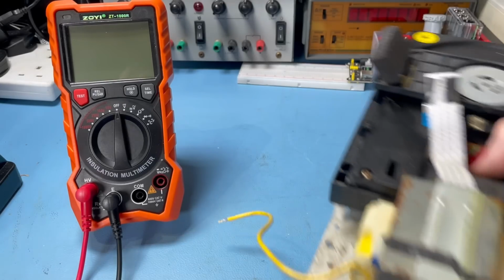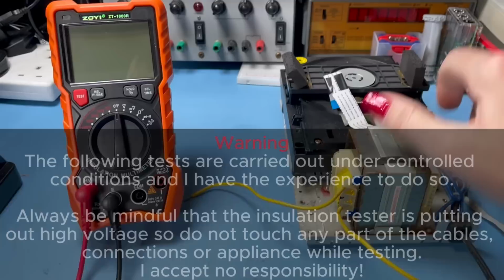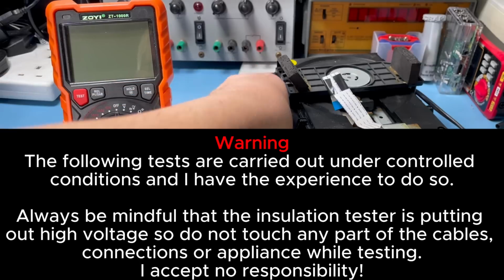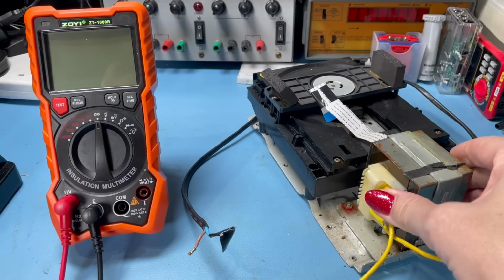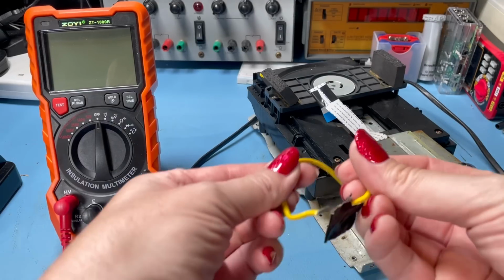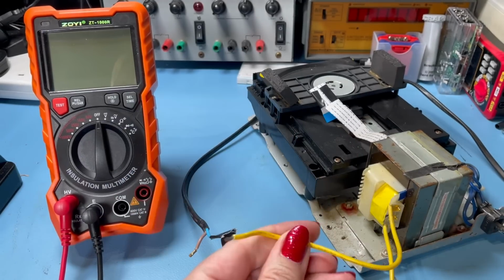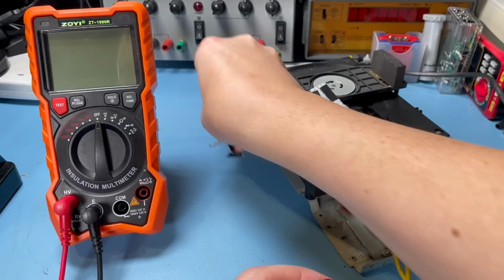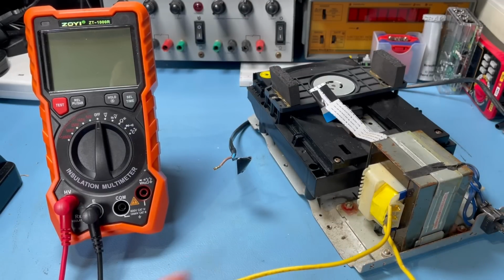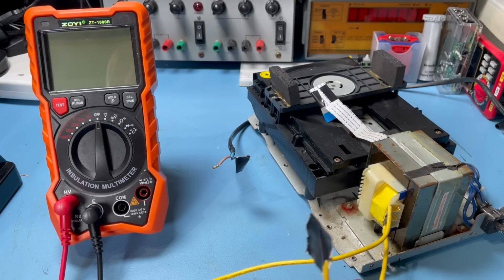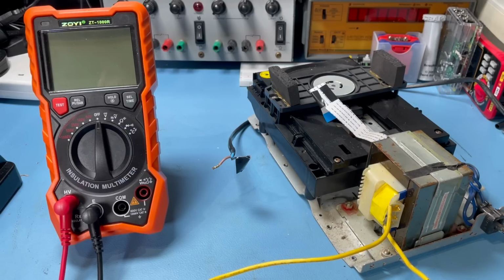So I've got a transformer here, which is still attached to part of an old CD player, would you believe? So we can use this. This is a good thing to test insulation resistance on. Now we want to make sure we're going across the transformer. You obviously don't want to be measuring like that, so we're going to go one end onto here and one end onto this, which goes to the other side of the transformer basically. And I've just taped off loosely the ones that I'm not using for testing.